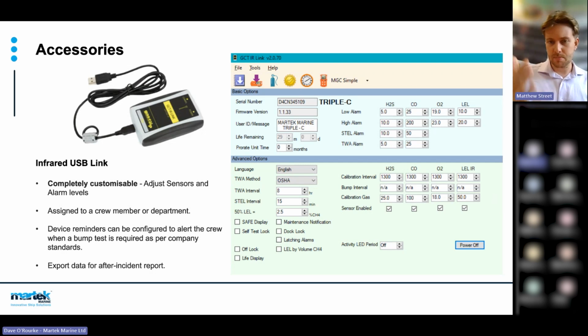You can adjust the bump test interval. You can see on there that's not actually set on the settings as standard. And the calibration interval as well, you can see is set for more days than the device will actually last for. Naturally, that is because it's not required to be calibrated.